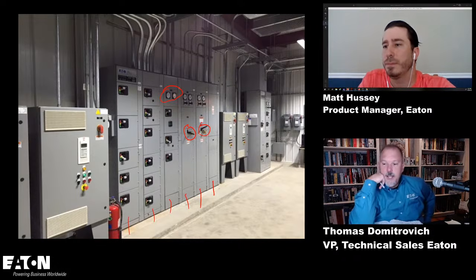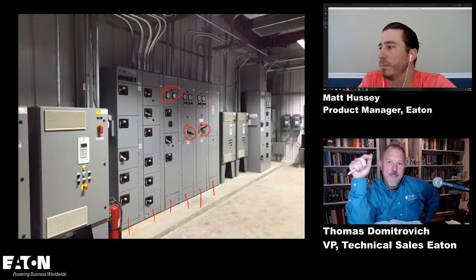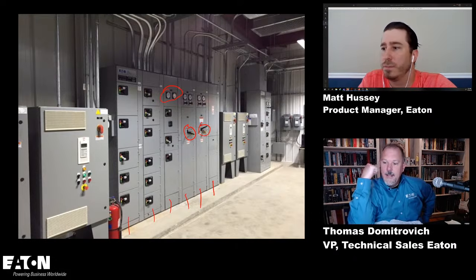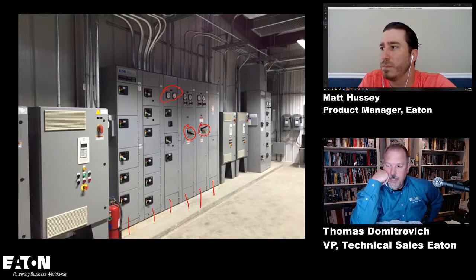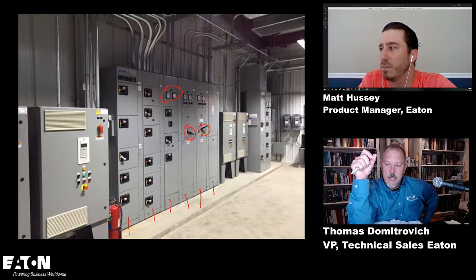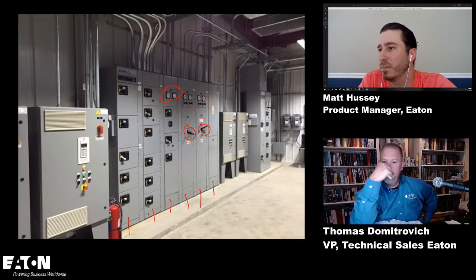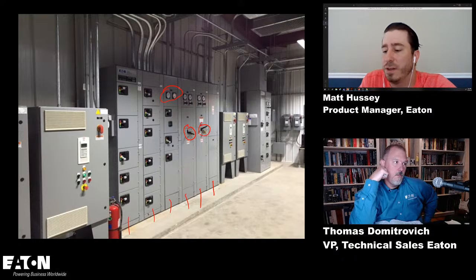So I'm looking at the chats because my browser's working finally. And Javier asked, can you put arc resistant back to back? Yeah, you can. Arc resistant constructions support the ability to provide containment for arc flash incidents that could occur in the equipment. And so a lot of the configurations allow for bolted back-to-back arrangements as well.